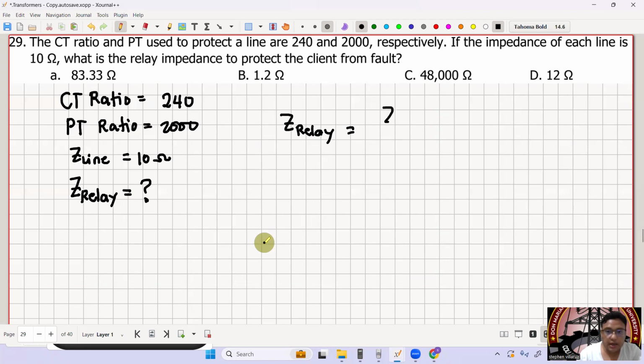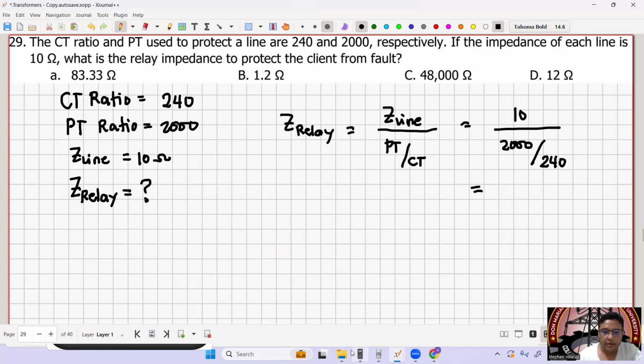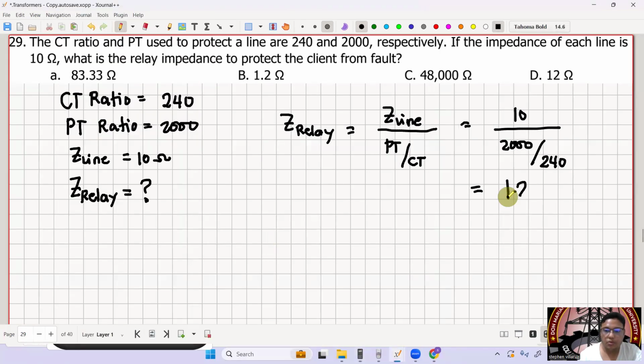is equal to your Z line over PT ratio over CT ratio. Okay? So therefore, this is now 10 all over PT ratio, that is 2,000, all over CT ratio, which is 240. So therefore, this is now 10 divided by 2,000 over 240. So therefore, this is now equal to 1.2 ohms. And this is letter B.